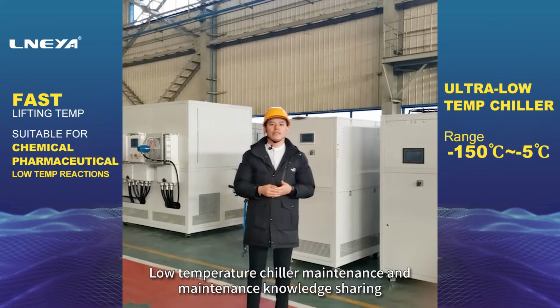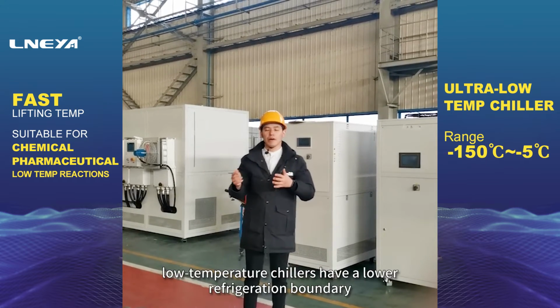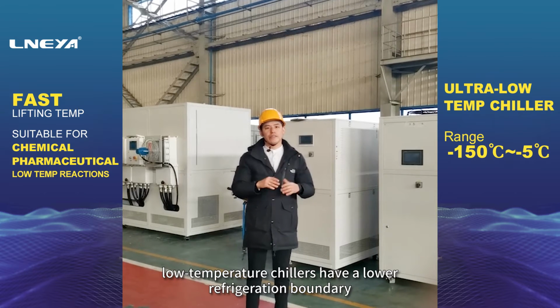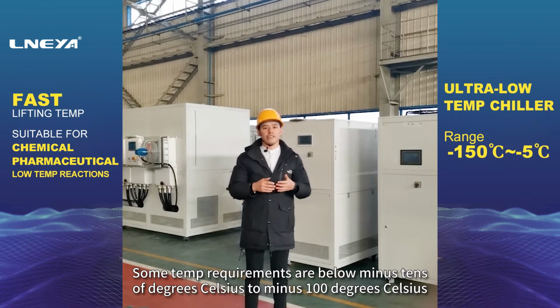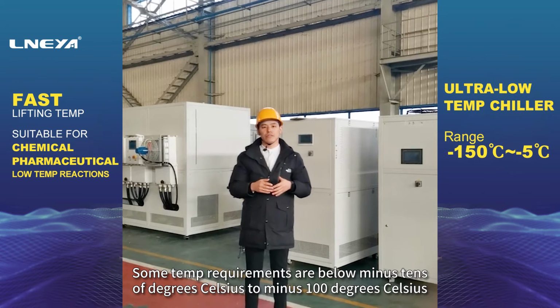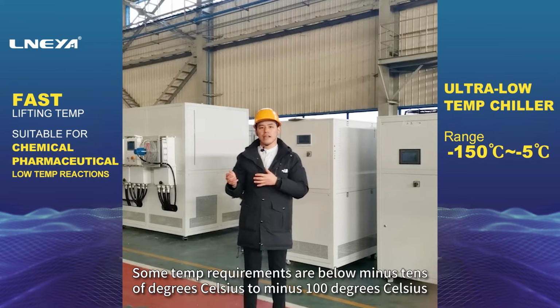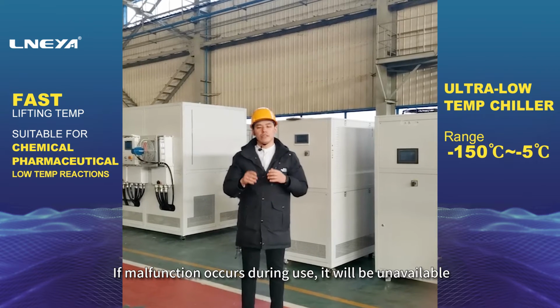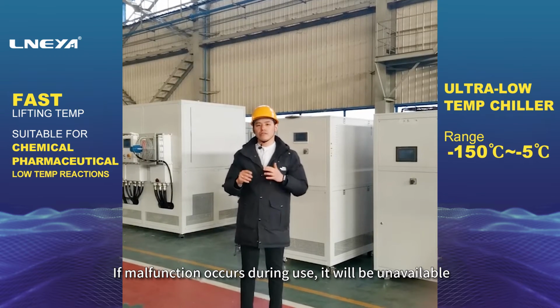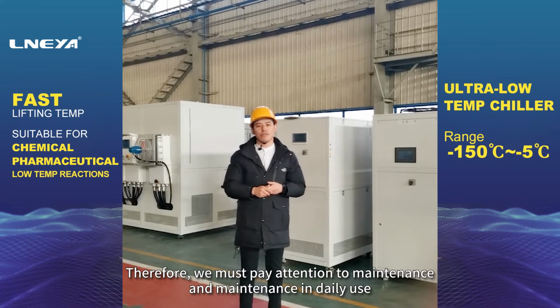Low-temperature chiller maintenance and maintenance knowledge sharing. Low-temperature chillers have a lower refrigeration boundary. Some temperature requirements are below minus tens of degrees Celsius to minus 100 degrees Celsius. If malfunction occurs during use, it will be unavailable. Therefore, we must pay attention to maintenance in daily use.